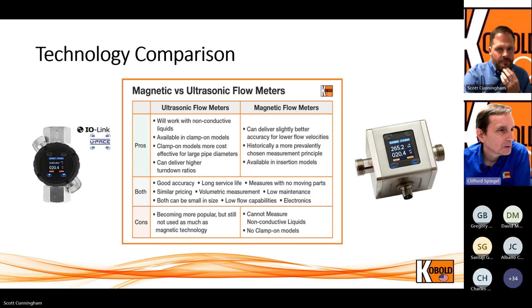Yeah, I don't know if you might have just addressed that with the clamp-on pipe ultrasonics having issues with the higher pipe skin temperatures. Let me look at the data sheet. 300F is pretty much the limit for the clamp-on ultrasonics. The flow-through ones, I believe, are less because the electronics are attached. Yeah, they're 194. So yeah, there are limits for either one.